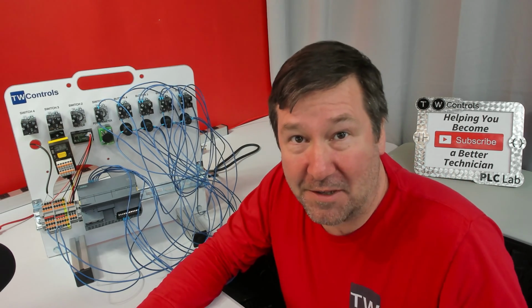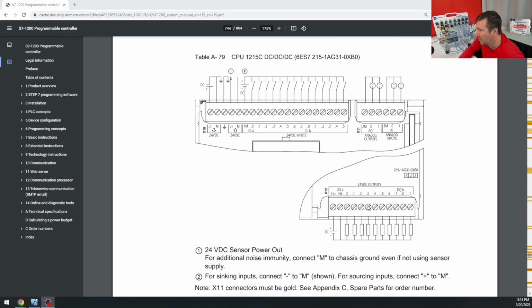And let's look at the manual, make sure we understand that. There's output 0 through 3 that we just landed the lights at. We're going to feed plus 24 to 4L plus. And very important, even though these are sourcing outputs, we still have to hook up this minus right here. So we're going to take 4M to the minus of our power supply.